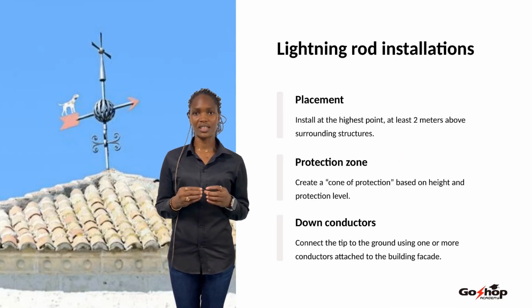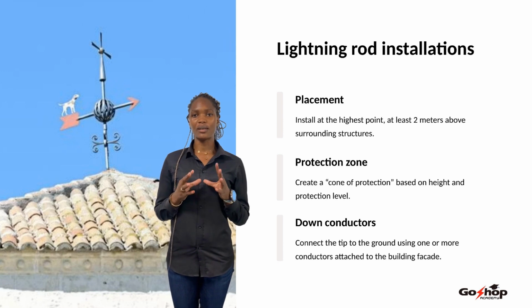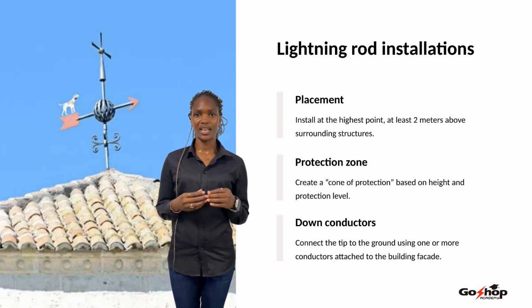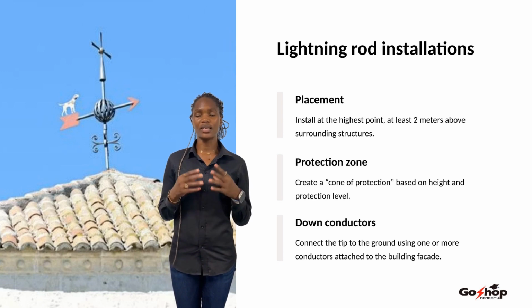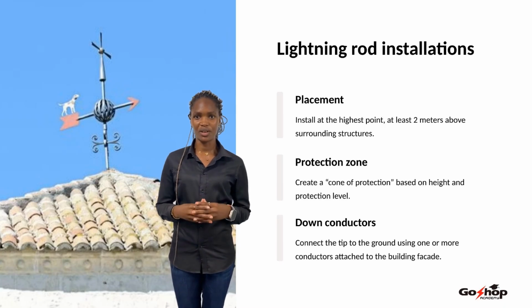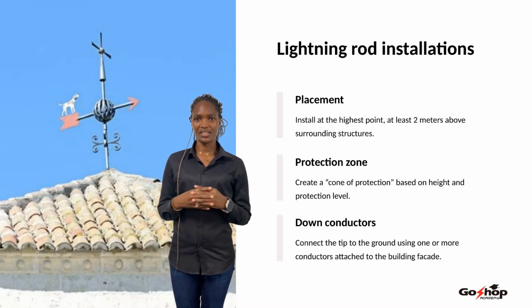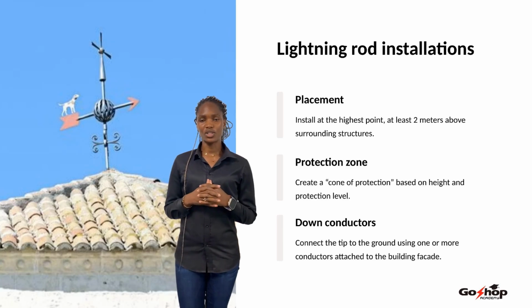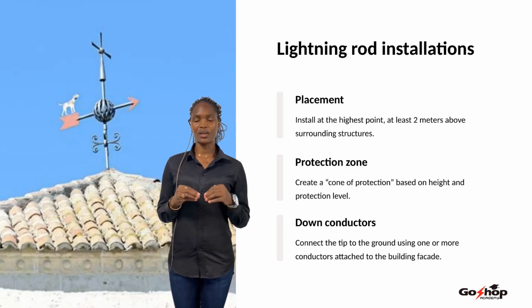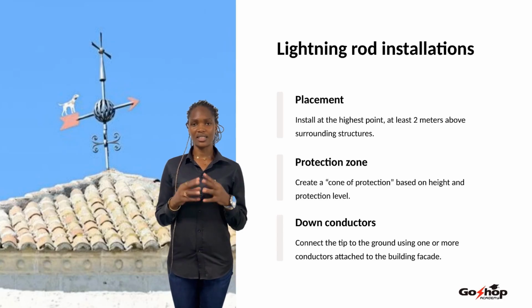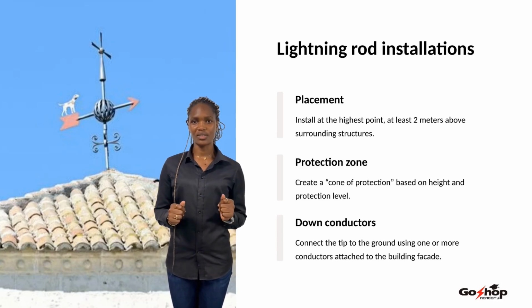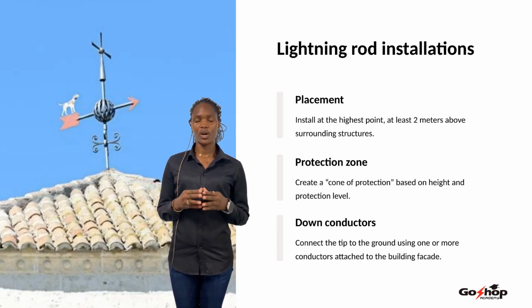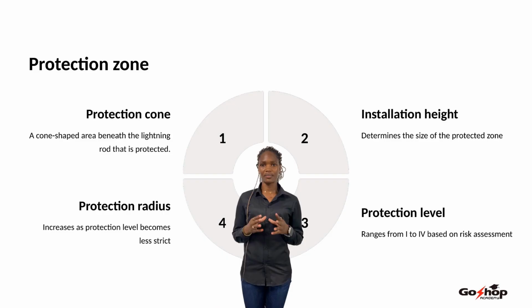To install a lightning rod, consider the following. Placement: install the lightning rod at the highest point of the building, at least 2 meters above surrounding structures. Protected zone: it creates a protection cone underneath. The higher it is, the larger the protected area. Down conductors: connect the rod to the ground using wires fixed along the walls. The shape and size of the protected area depend on height and chosen protection level.